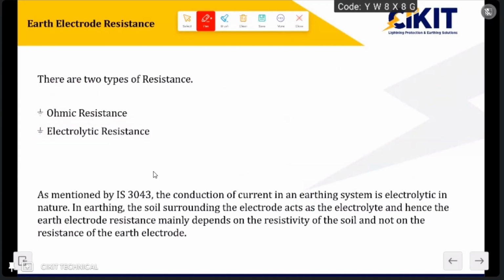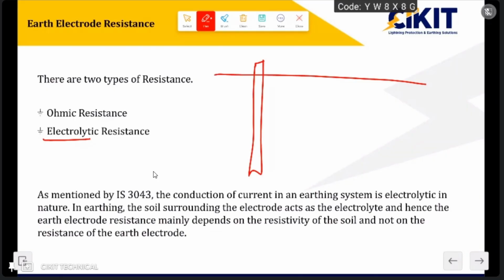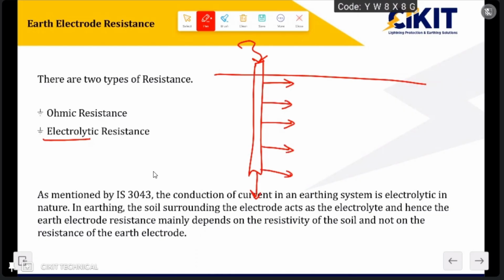But the second type of resistance is electrolytic resistance. In electrolytic resistance, for example, if I take earthing as an example, if fault current is flowing to this earth electrode, the dissipation will be taking place from this earth electrode to the surrounding soil. So here the dissipation takes place from one medium to another medium. So here the surrounding medium plays an important role. So in an electrolytic resistance, the conduction is taking place from one medium to another medium, and if the surrounding medium is having very high resistance, then the discharge won't be proper. So in electrolytic resistance, the surrounding medium plays an important role.